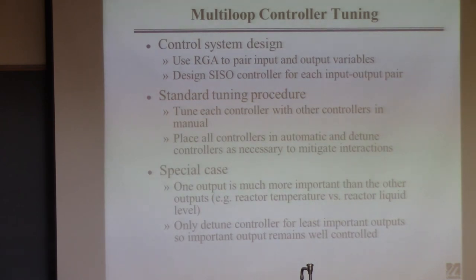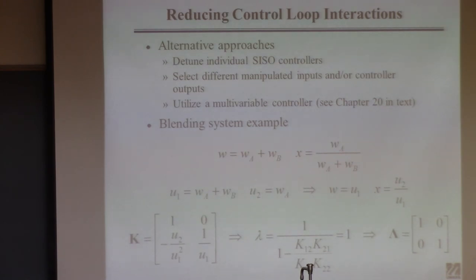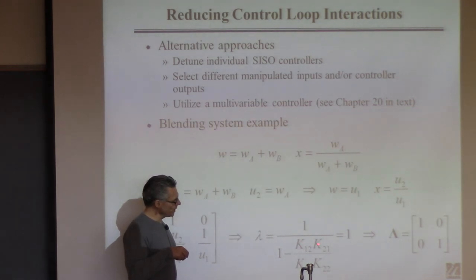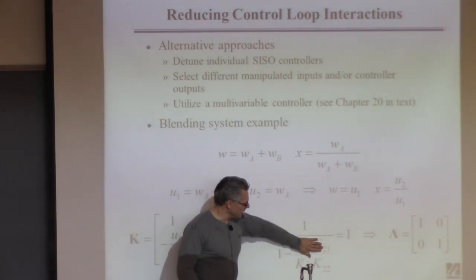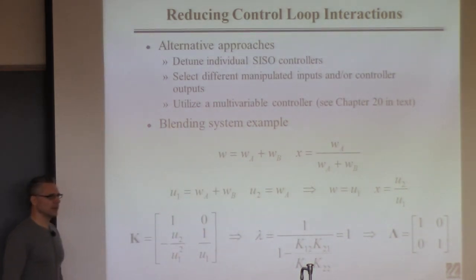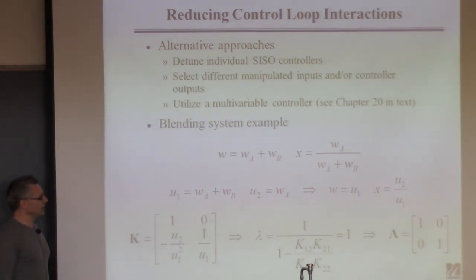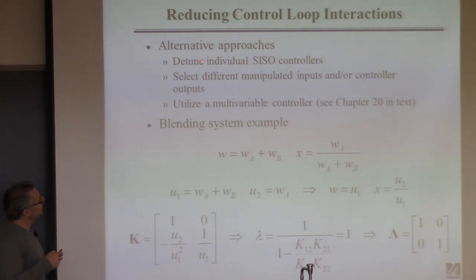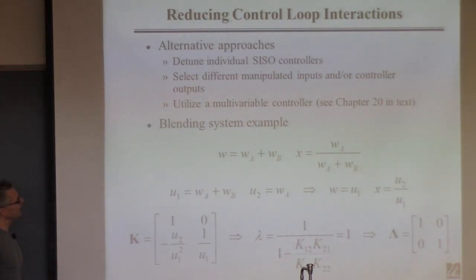Here's another special case: suppose you need to control reactor temperature and reactor level. These two things are going to interact — if you have more inventory in the reactor, more level, it's going to generate more heat and affect temperature. But the temperature is a lot more important than liquid level. So you design both controllers, turn them on, they interact, and then you just detune the liquid level controller. Don't sacrifice reactor temperature control because it's important — sacrifice liquid level control because it's not.